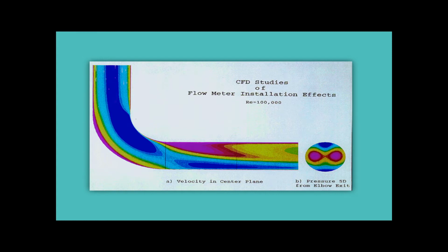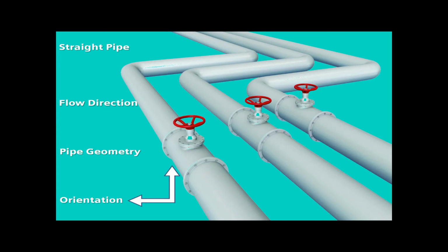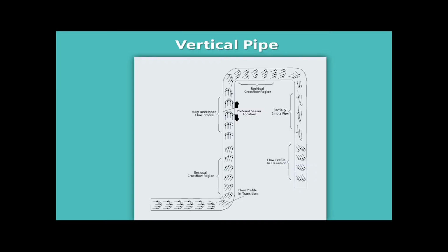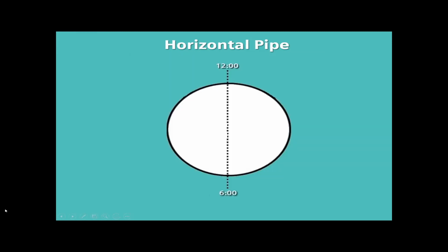And of course, there's also pipe orientation. Is the pipe vertical or horizontal? Well, either is okay, so why do I even mention it? There are still considerations. If the pipe is vertical, it is preferred that the flow is upward. Downflowing sections can result in shearing of the flow, creating voids that will interfere with proper measurement. On horizontal pipes, the flow sensors should not be installed on the vertical center line, 12 o'clock or 6 o'clock, where the potential for air or sediment exists.